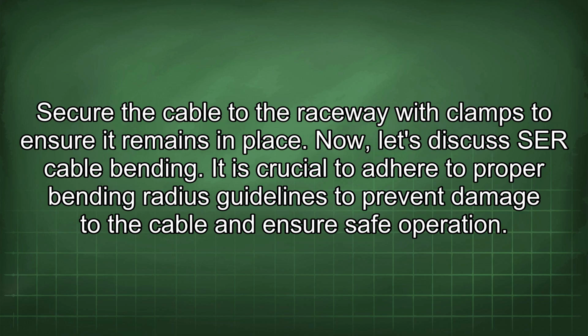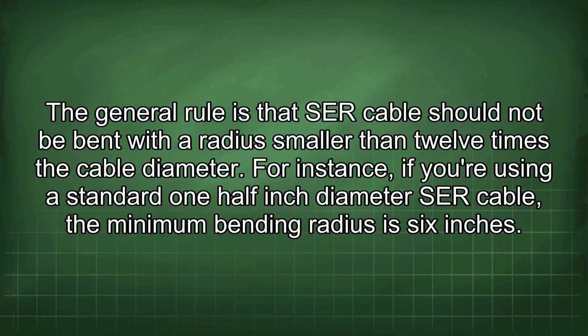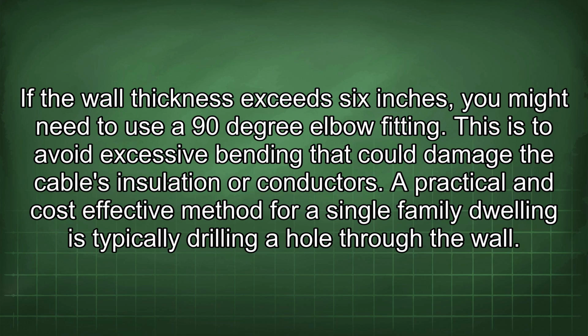Now let's discuss SER cable bending. It is crucial to adhere to proper bending radius guidelines to prevent damage to the cable and ensure safe operation. The general rule is that SER cable should not be bent with a radius smaller than 12 times the cable diameter. For instance, if you're using a standard 1/2 inch diameter SER cable, the minimum bending radius is 6 inches. If the wall thickness exceeds 6 inches, you might need to use a 90-degree elbow fitting. This is to avoid excessive bending that could damage the cable's insulation or conductors.